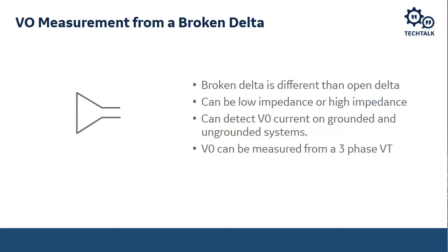When you have a phase to ground fault in an ungrounded system, you're going to have elevated phase-to-phase voltages on the unfaulted phases, and zero voltage on the faulted phase because that voltage is now grounded. So I'm going to have a high level of zero sequence voltage, which I can easily detect. In a normal balanced power system, my zero sequence voltage is 0, because my phase A, B, and C voltages are balanced, 120 degrees out of phase with each other, and the magnitudes are pretty much the same. So when I do this calculation for the zero sequence voltage, it will be 0. But we still have the problem of detecting where that ground fault is. A zero sequence overvoltage just tells me I have a ground fault within my system. It will not tell me where that ground fault is.